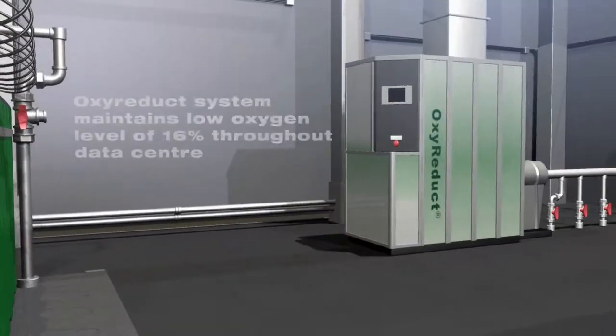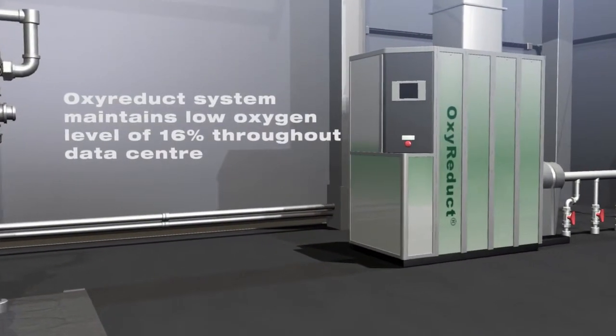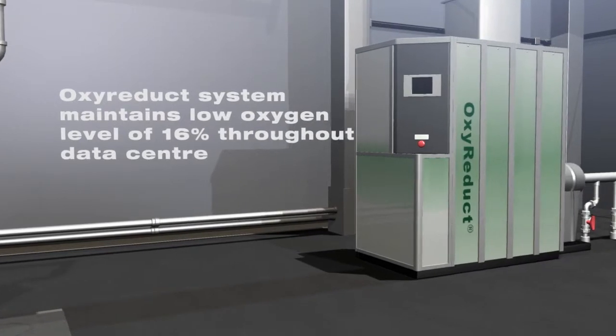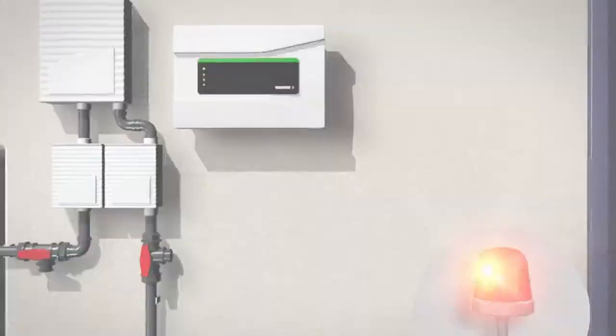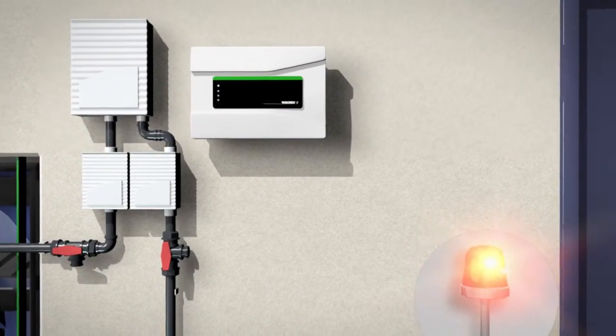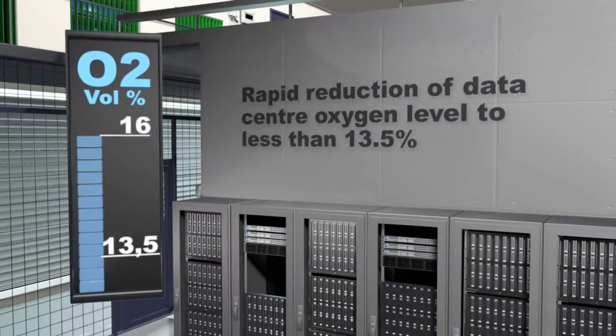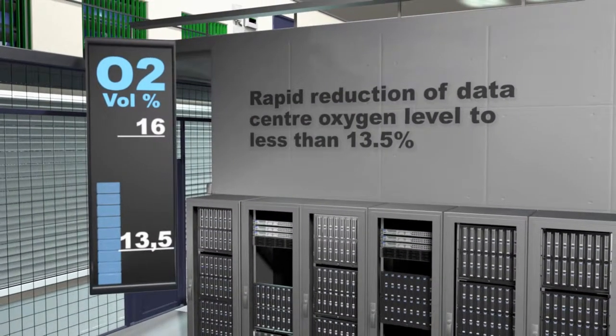The data center's oxy-reduct units ensure that the oxygen concentration remains constant at this low level. If the fire risk does not decrease, the oxygen volume is rapidly reduced even further to a level of 13.5%.